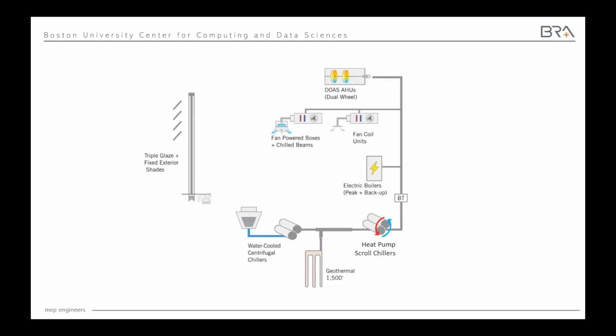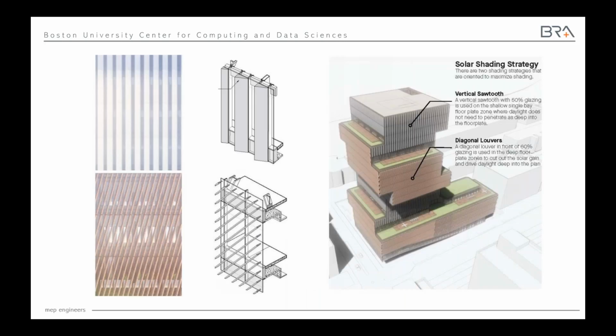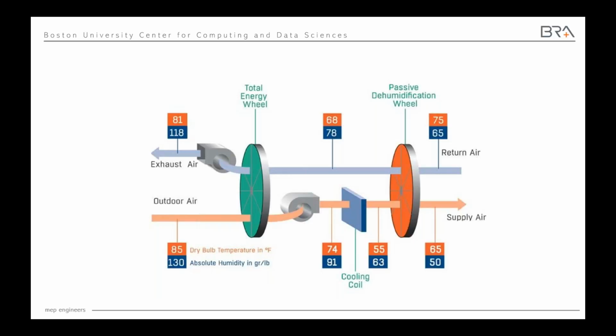In the last option, we have that left-hand choice of having a centralized heat recovery chiller system that sends chilled water and hot water out to the building. And then we have electric boilers for peak and backup, and that means there is literally no gas connection to this building at all. There was a lot of focus put into the envelope. It was tuned by orientation and by depth of floor plate to have different amounts of glass and different amounts of shading and different shading geometry. We've got our friend here, our dual wheel for ventilation heat recovery.